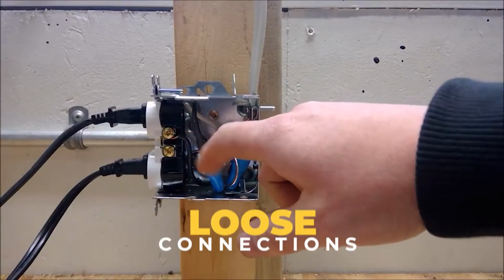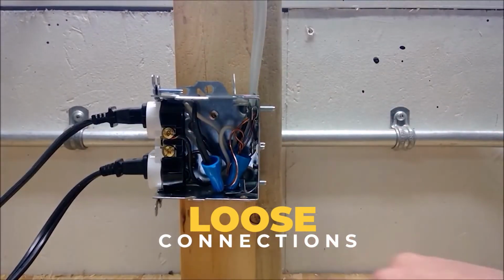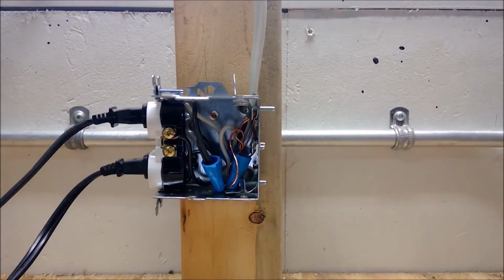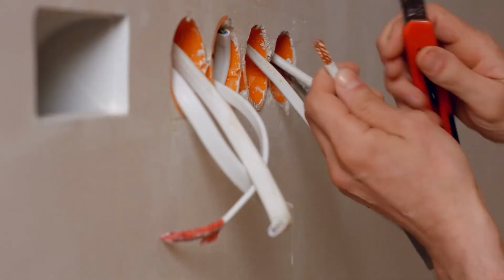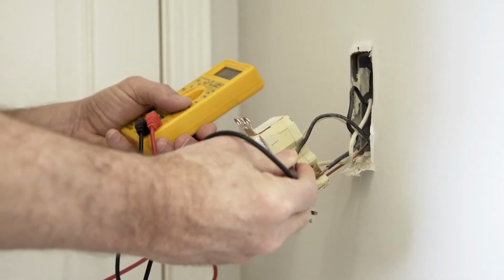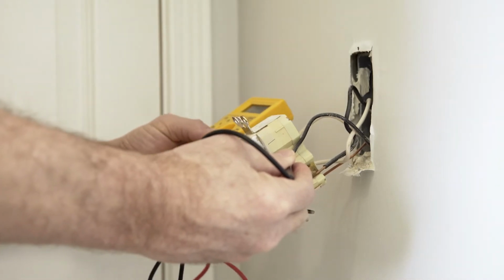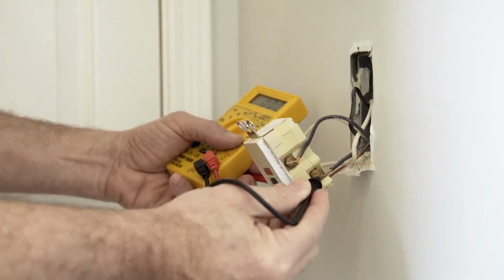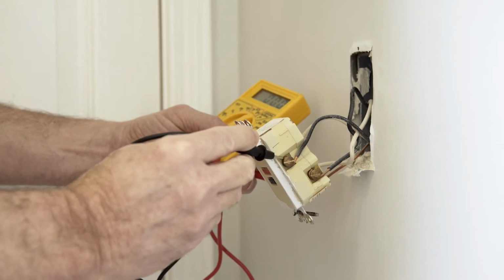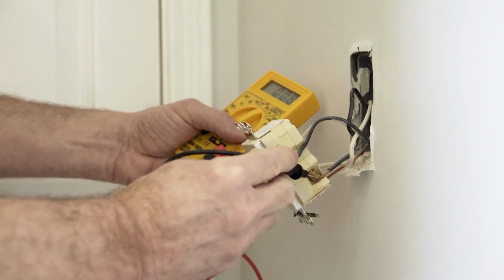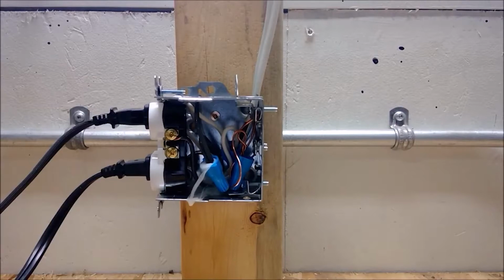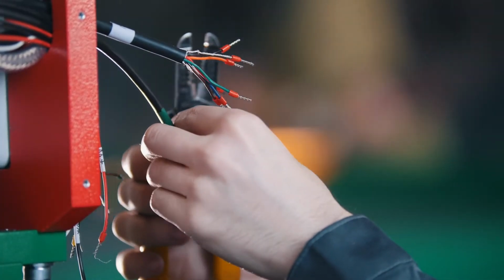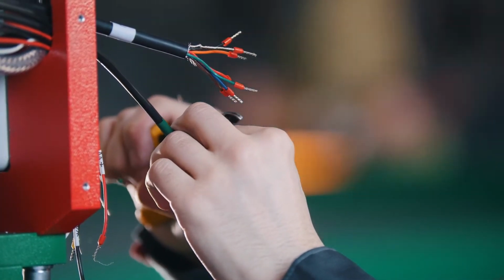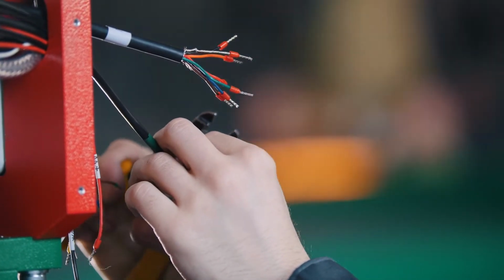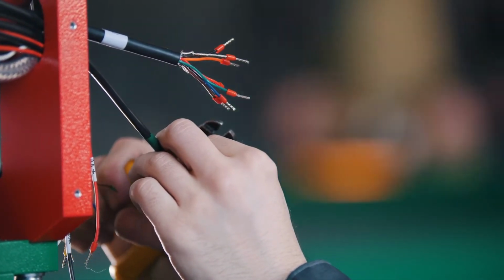Loose connections. Loose connections are frequently the result of rushed labor if a crimping tool is not readily available. Cable lugs are sometimes poorly crimped with side cutters or combination pliers. If good care and carefulness is not taken to establish watertight connections, even when someone's under pressure, especially when working on essential equipment, weak connections will be recognized later when cables begin to overheat and decolorize. My advice is to properly tighten all connections to ensure that all connection resistances are eliminated and to use the appropriate equipment for each job.